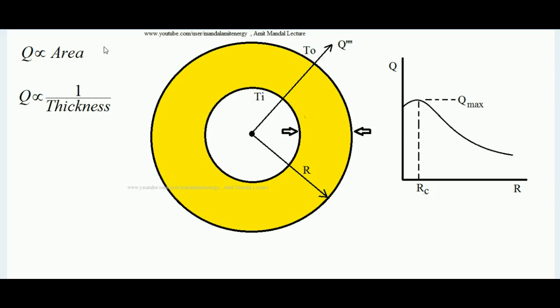So what will happen — will the heat transfer rate increase due to the increment in outer surface area, or will it decrease due to the increasing thickness of insulation? The answer is that up to a particular limit, the effect of increasing area of exposure prevails over the resistance of increasing thickness. Up to that limit, the heat transfer rate will actually increase. Beyond that threshold, with further insulation applied, the heat transfer rate starts reducing, as shown in the graph of heat transfer rate versus insulation radius.